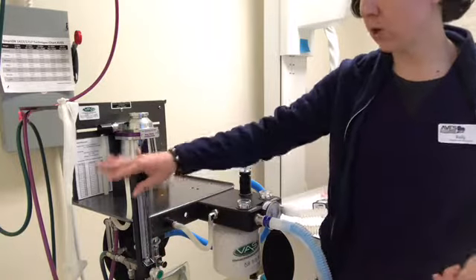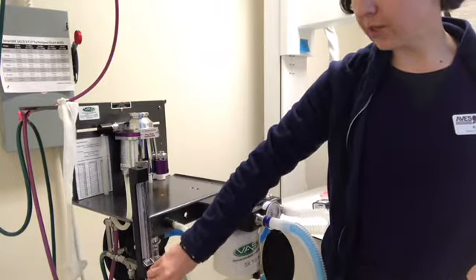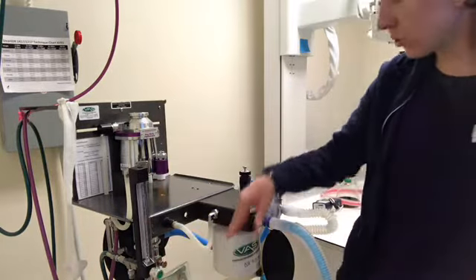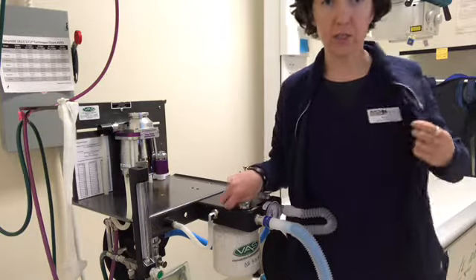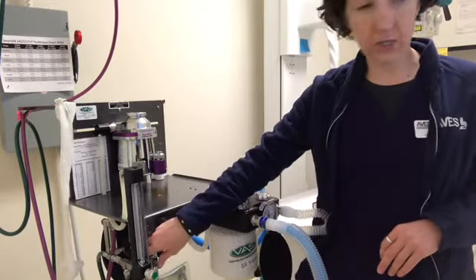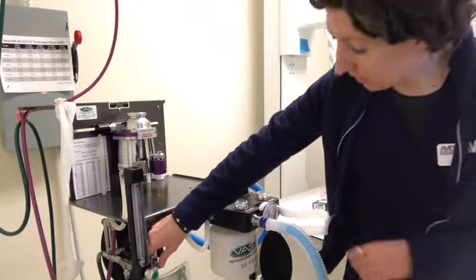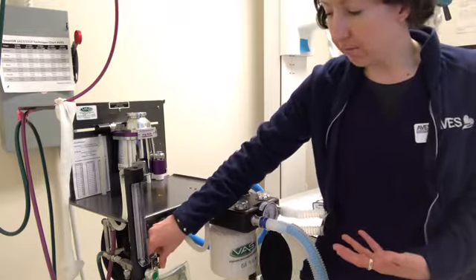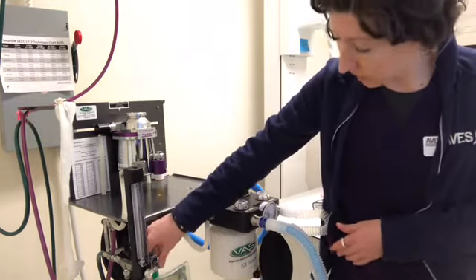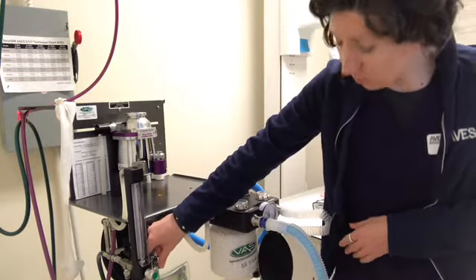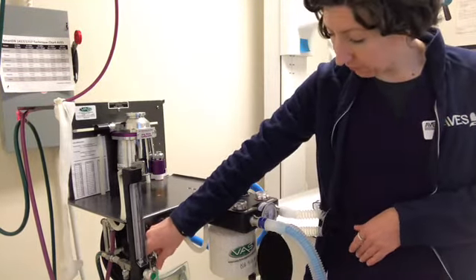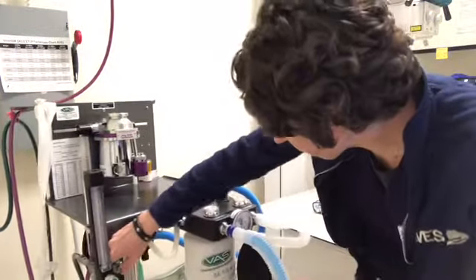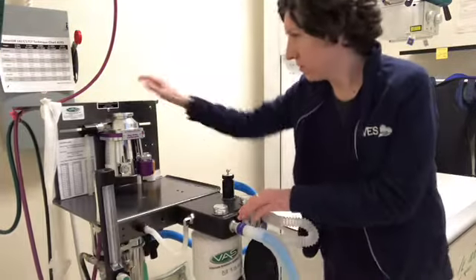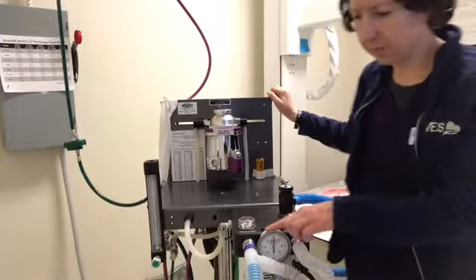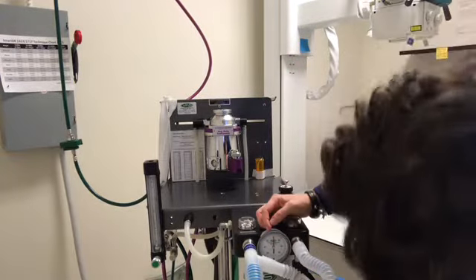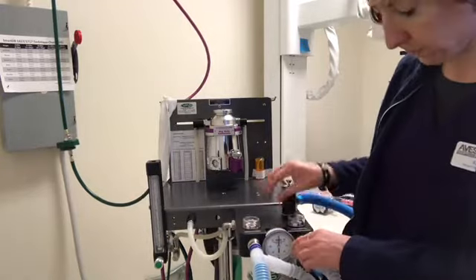So it is quite a bit stronger than what we can use with our flow meter. So you need to be very careful when you're using that, because you can damage the patient's lungs. When using the flush valve, because of the strength of the oxygen coming through, you want to use it in short little bursts. Again, that will help keep your patient safe. And when you are pressuring it, this is the manometer, and this will tell you the centimeters of H2O of the pressure.